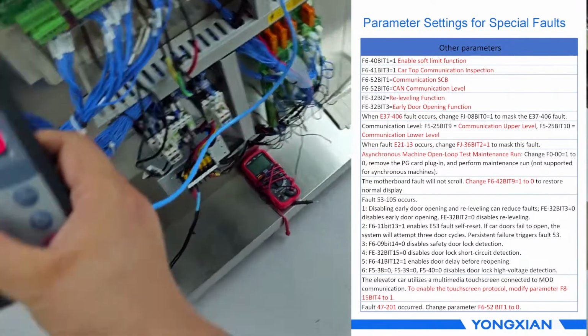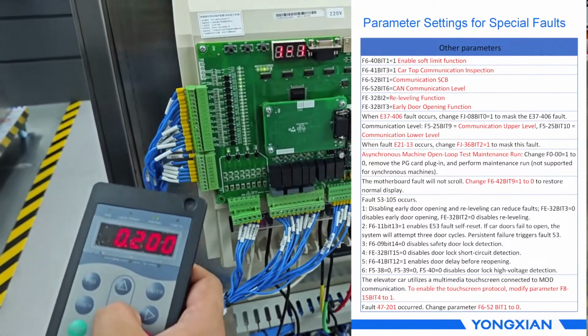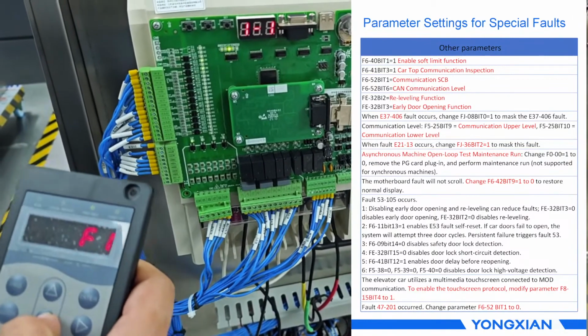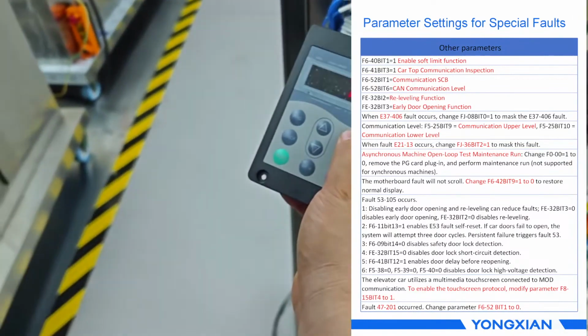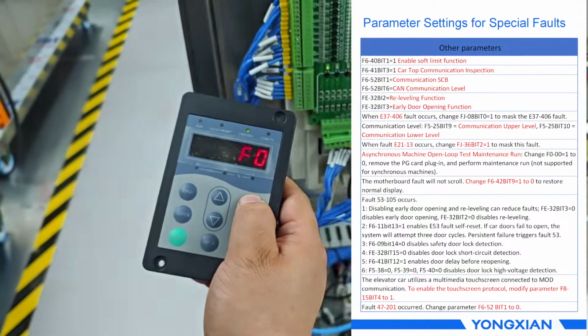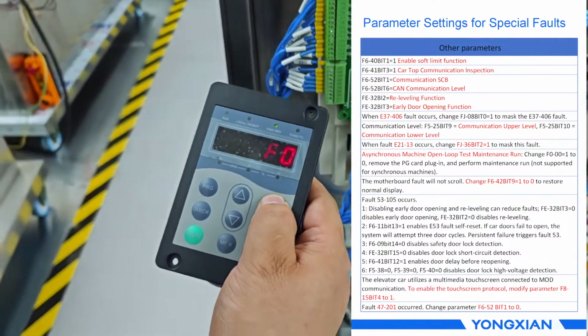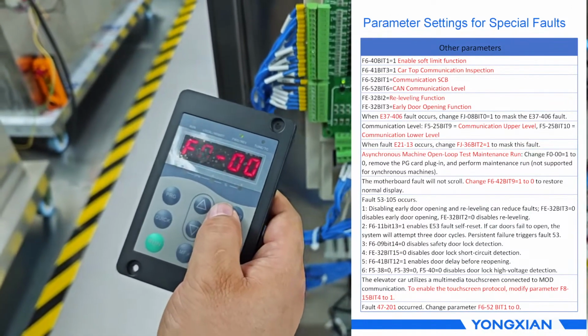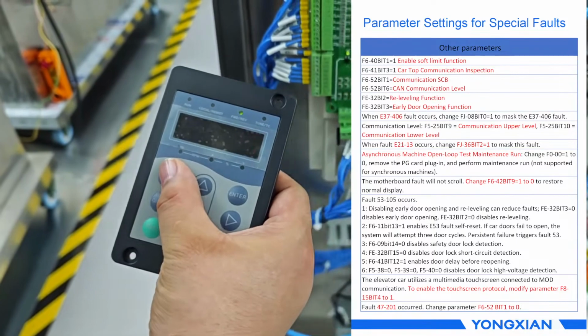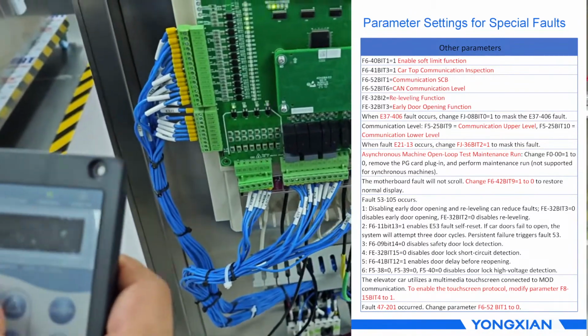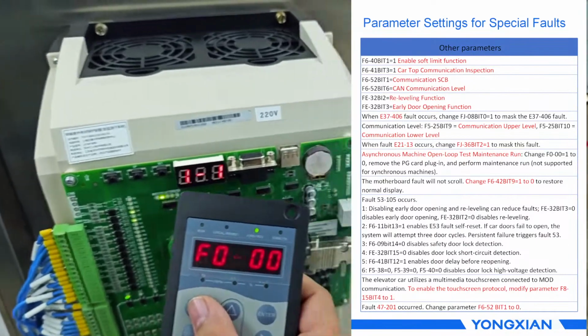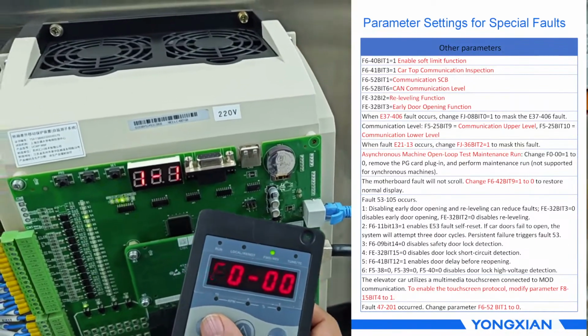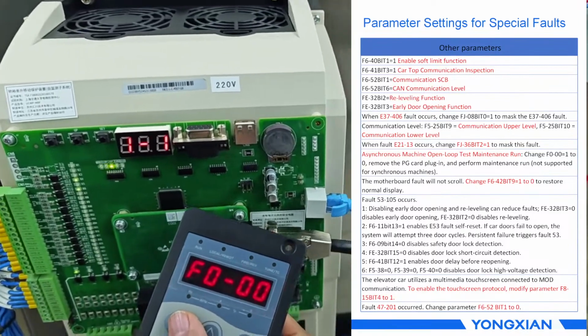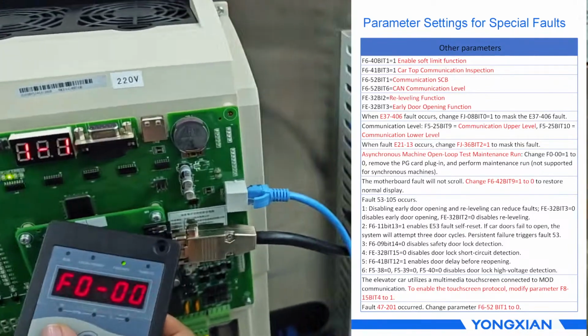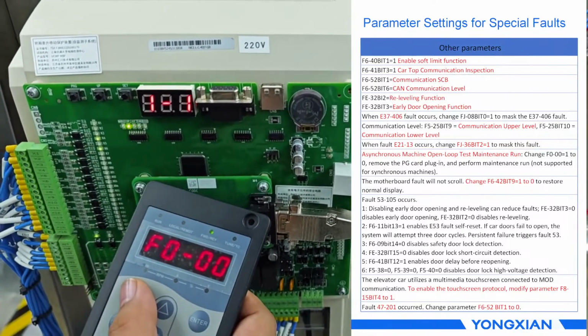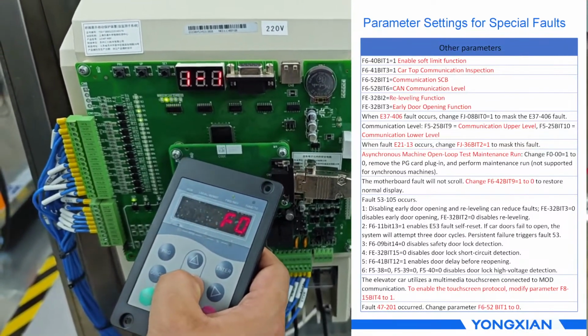下一个是我们的一个异步电机的一个开环检测。Next is our asynchronous machine open loop test maintenance run. 将 F0-00 改为1改为0。Change the F000 equals 1 to 0. 可以拔掉我们的 PG 卡检修运行。Remove the PG card plug-in and perform maintenance run. 同步电机不支持。It is not supported for synchronous machines.